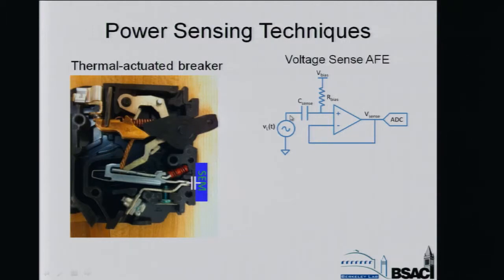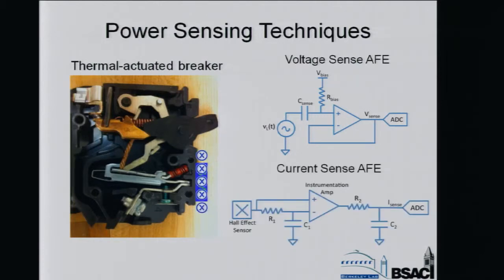And so that capacitor current is converted to voltage, amplified, and then digitized by an ADC. I call this signal Vsense, and this Vsense signal is then proportional to the derivative of the circuit breaker's line voltage. Now, to measure the current, we monitor the magnetic field incident on our Hall effect sensor. So you can see the circuit here. There's a Hall effect sensor, some filtering, an instrumentation amplifier, and then that signal is digitized by the ADC on the MSP430. And I'm going to call that signal iSense.